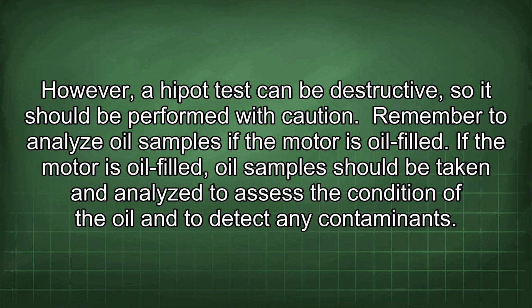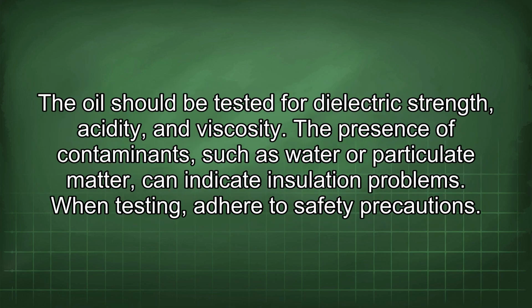Remember to analyze oil samples if the motor is oil-filled. If the motor is oil-filled, oil samples should be taken and analyzed to assess the condition of the oil and to detect any contaminants. The oil should be tested for dielectric strength, acidity, and viscosity. The presence of contaminants such as water or particulate matter can indicate insulation problems.